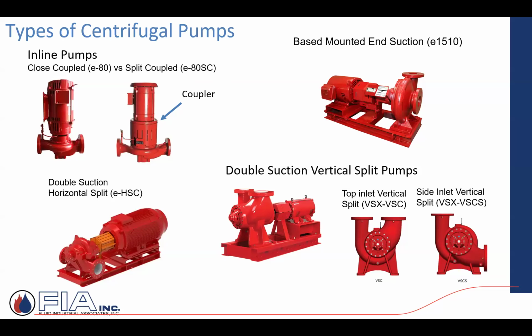Very, very common. As you move into some of the larger capacities, you get into these bigger campuses, you're just dealing with bigger loads, bigger flow rates. That's when you get into the double suction, and we'll talk a little bit more detail about that. But the double suction, whether it be horizontal split over here on the left, or the double suction vertical split pumps, there's a couple of different orientations, and we'll get into that as well.